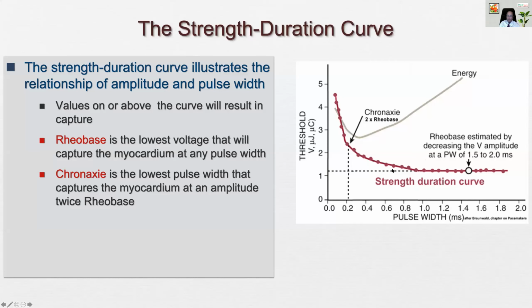There are two important points that we can derive from the strength duration curve. One is the rheobase, which is the lowest voltage that will capture. Even if you keep on increasing the pulse width to infinity, it will not change. That is called rheobase. And chronaxie is the lowest pulse width that captures the myocardium at an amplitude twice the rheobase. So this is the rheobase level, 1.2 in this case, and 2.4 becomes twice the rheobase. Chronaxie is the minimum pulse width that will capture at that amplitude. So these are the two important figures.